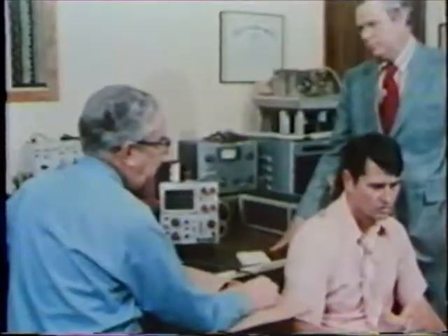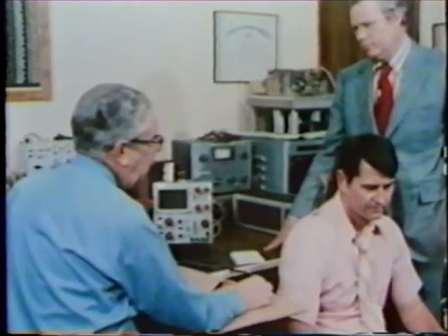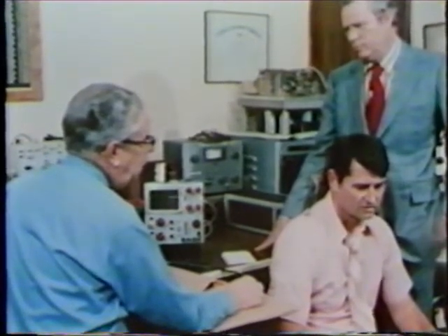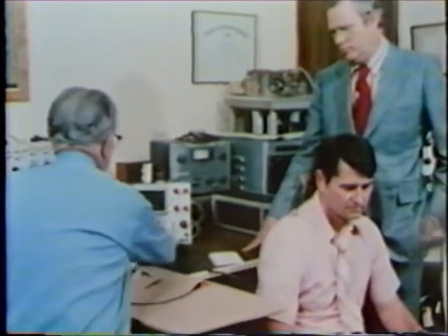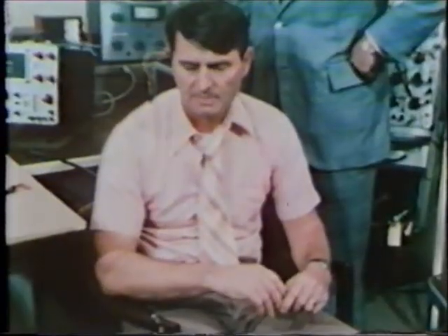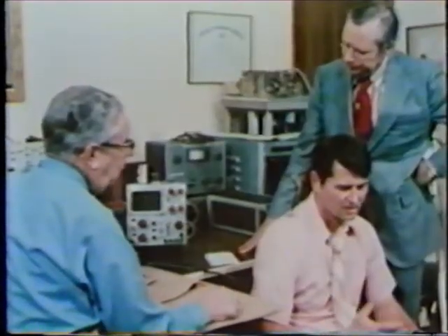During our investigation, we were very careful to be sure that all of our equipment was properly isolated. We used isolation transformers to supply all the necessary voltages for our equipment, and also we used isolation mats to protect Mr. Grazer from being in contact with the floor where he could possibly pick up some stray currents.